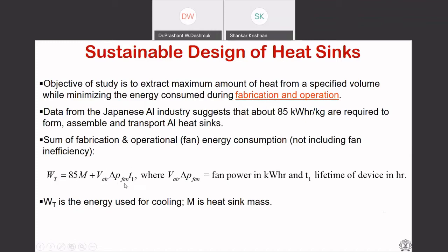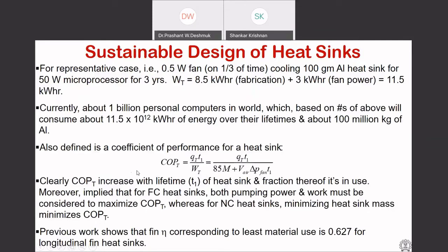So 85 kilowatt-hours per kilogram times the mass gives the energy consumed during the fabrication process. The second part is the power consumed during operational needs — that's the overall energy. If you don't have a fan, then all you have is the fabrication term. We can write a COP — coefficient of performance — for a heat sink, defined as the benefit divided by work consumed. It is quite well-done work; I'll share the paper with you.